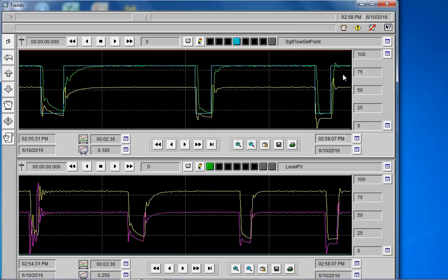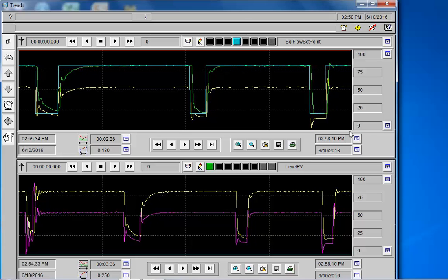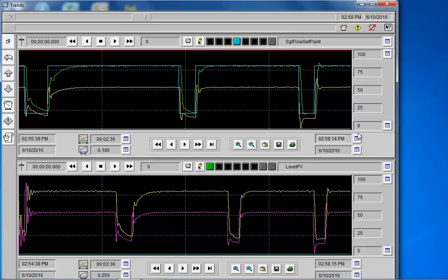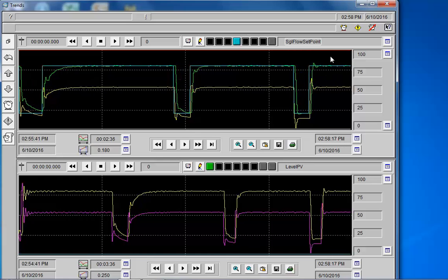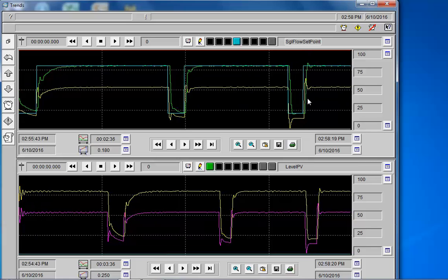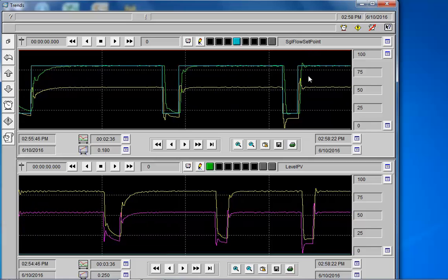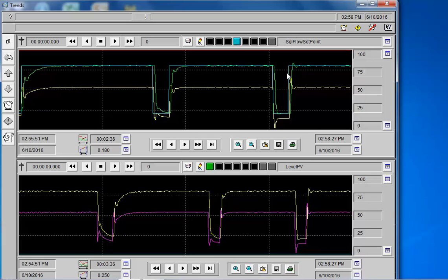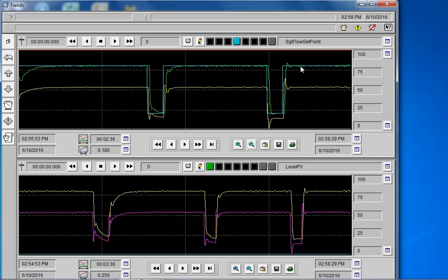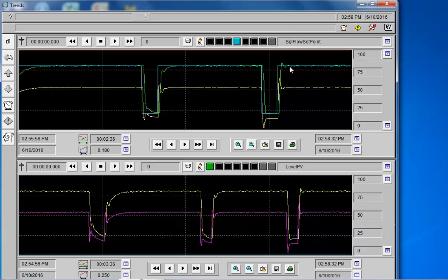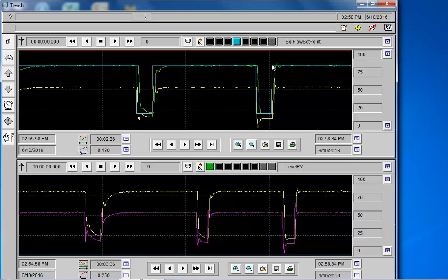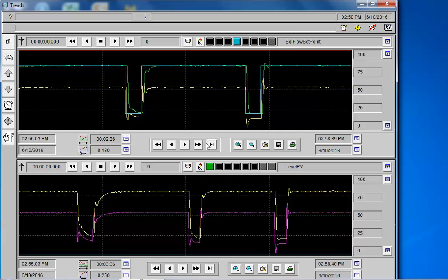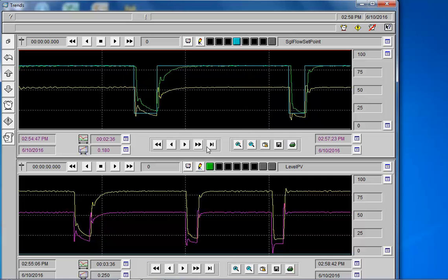Now, this last response here, asking the questions, is it fast, is it accurate, and is it stable? We are getting close. We've got something which is achieving a set point in quick time. We have a on set point, so it's accurate, and we have reasonable stability. Now we also look at chasing a slightly underdamped response with overshoot no more than 5%.